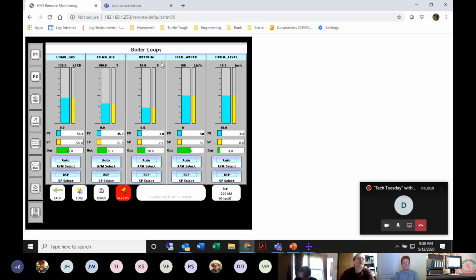Boiler control loop. So this would be an example. Let's say I had a system, an oven, a heat treat oven, or an application that had several process control loops. Let's say I had an old panel that had 5 UDC controllers. This faceplate will allow you to place those UDC controllers into segments on the display so that you can see individual control loops all at the same time: what the process variable and set point are, and what the percent outputs are. This gives you a very nice overview window of what's going on with the process and allows quick access into it.